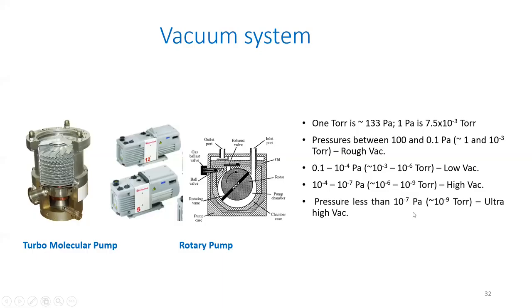And again, you need a very good vacuum system. As I said, typically you have turbo molecular pumps, which can be compared with the engine of a jet engine. So this is a turbo molecular pump, and you have rotary pumps in SEMs as well. And these are the vacuum levels in the microscope. Typically for field emission guns, you need ultra high vacuum, like 10 to the power minus 7 pascals is what you're looking at. But for tungsten filaments, it is useful for most applications, low cost, and the vacuum levels are not that demanding. So it depends on the application, how you would like to configure your SEM.